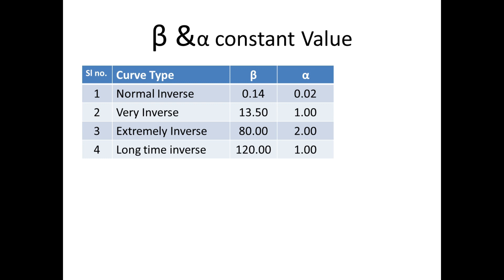When we substitute these values in the formula, for normal inverse we get: T equals TMS times 0.14 divided by (Ia/Is) to the power 0.02 minus 1.